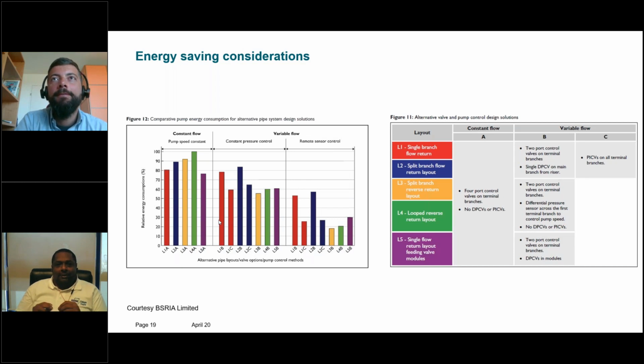Allow me to elaborate a little bit more on this question, because it is typically here. We have the district cooling provider, they are applying low delta T penalties on the customer who brought low delta T. So I think this will add more advantage by using an intelligent PICV, because it will help the owner of this building to avoid the low delta T. It will add more in the costing, because he also pays low delta T penalties to the district cooling provider, in addition to the normal saving you get in the energy consumption itself. So you are saving energy on one side, and you are saving the penalties, which will add an advantage for such intelligent PICV valves.